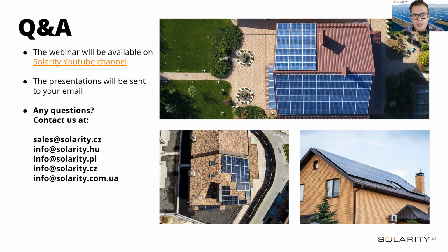Can you explain again how to size the battery for PV? I already replied that if you have a 10 kilowatt installation, make sure you have about 10 kilowatt hours of battery. If you don't have the funds for a 10 kilowatt hour battery, you can install, for example, 6 kilowatts, based on your demand - if you need less, install less. If you want to expand later with an EV charger, you can add an extra battery pack. But just don't oversize.